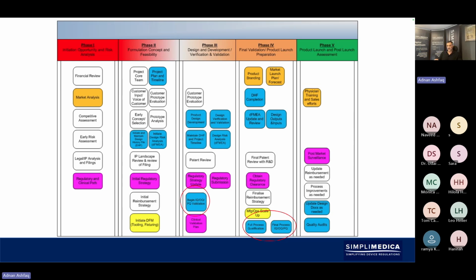But verification and validation is when you would typically begin your IQ, OQ, PQ validation. And when you get ready to do your final validation, you will do full process validation and final process IQ, OQ, because you also have to do a design transfer. So when you're doing your design transfer, you've gone effectively from a design freeze of a medical device into production, from a lab scale prototype manufacture type of environment into full scale production.